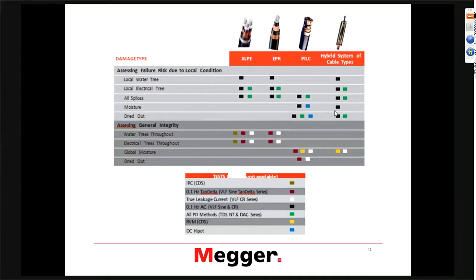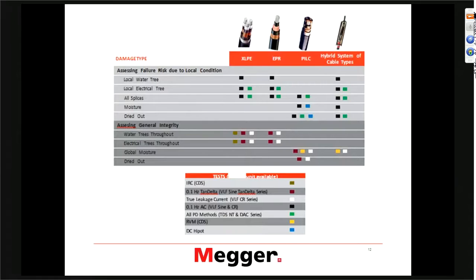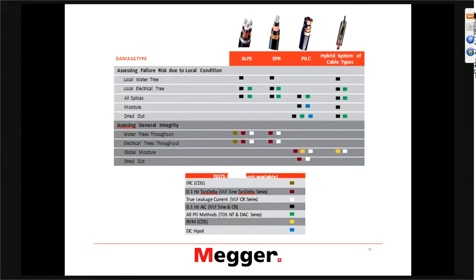This chart shows what type of defects you might have in certain type of cables. Paper cables don't show any water trees, but all cables show the same issues with splices. Some testing methods are very specific to specific defects. The Tan Delta is very specific to the aging condition caused by water trees — that is the big benefit, because we have so many XLPE cables in the field today that we want to monitor the aging condition and make replacement decisions.